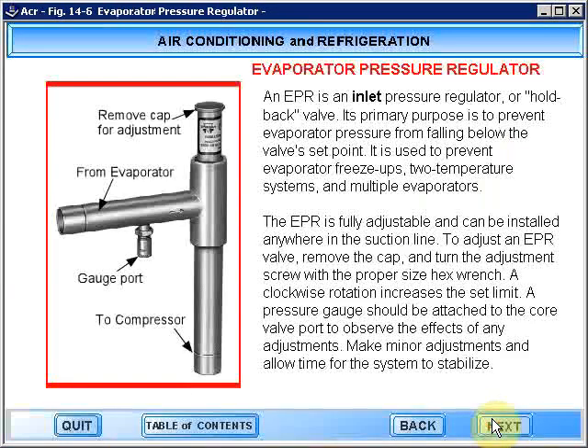An evaporator pressure regulator is an inlet pressure regulator or holdback valve. Its primary purpose is to prevent evaporator pressure from falling below the valve's set point. It is used to prevent evaporator freeze-ups on two-temperature systems and multiple evaporators. The EPR is fully adjustable and can be installed anywhere in the suction line.